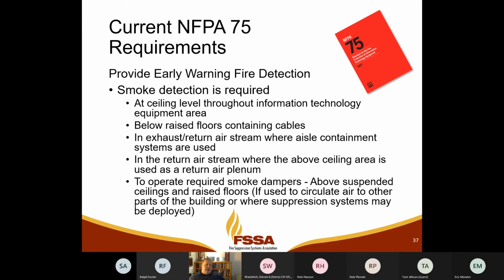In the exhaust, third point here, in the exhaust return air stream where aisle containment systems are used. Basically, what that Research Foundation project showed is that at early stages of the fire, the HVAC air patterns influence the smoke movement much more than the buoyant forces of the smoke from the fire would. So most incipient fires in a data center where smoke is being produced, because of the high air change rate and a large amount of cooling, that smoke's going to be cooled down quickly. Its buoyant energy is not going to be enough to overcome the HVAC air patterns.